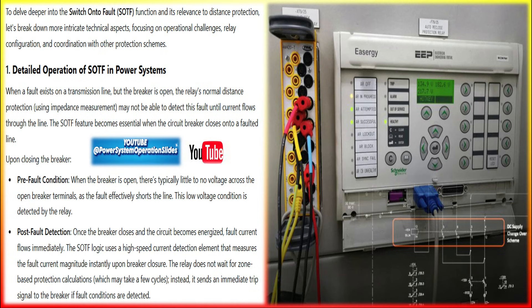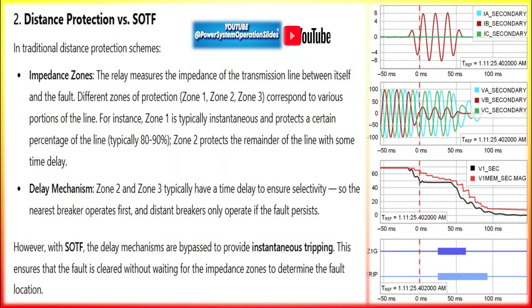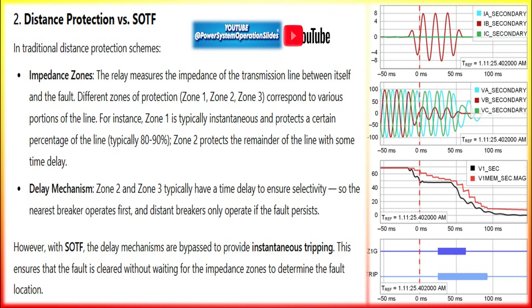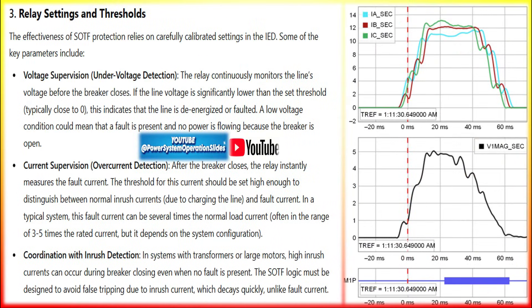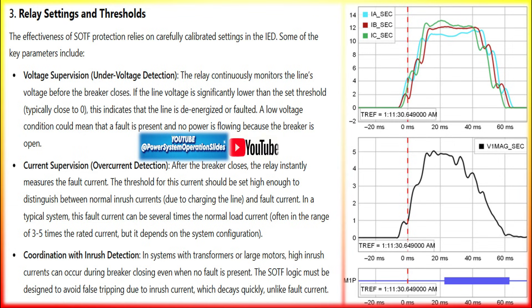For breaker closure detection, the relay detects when the circuit breaker is about to be closed using breaker status contacts or auxiliary contacts. At this point, the relay prepares for potential fault detection. Once the breaker closes, the relay looks for a sudden spike in current. If the current exceeds a preset threshold — much higher than normal load current — it assumes that the breaker has closed onto a fault. The SOTF function then bypasses normal protection settings like time delays or zone coordination and sends an immediate trip signal to isolate the faulted line.